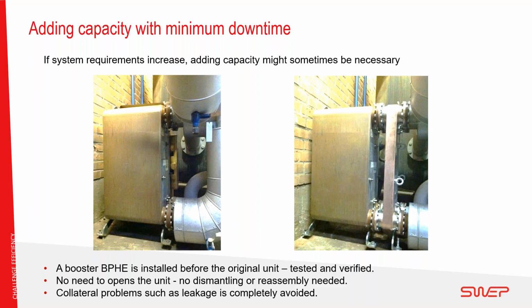And of course, you've got a 100% pressure tested, certified heat exchanger that just simply bolts on. Very little extra labor work required, no pipework modification. It's just basically pushing the existing unit back and slotting in this booster unit. So we can address that additional capacity on the large scale heat exchangers quite well.